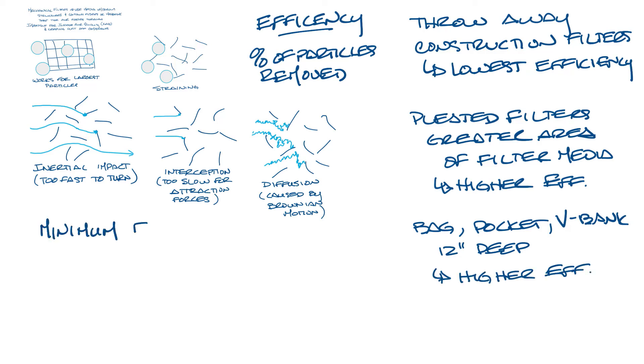You'll see filters rated with a minimum efficiency reporting value or its MERV value. So you'll see MERV 8, MERV 13, and so on to MERV 16. For the filter types we just discussed, the throwaway filters are typically a MERV 5 or lower. Pleated filters are around MERV 6 through 11. And the V-bank type are usually MERV 11 through 15. I'll do a separate video on MERV and particle size and go into a lot more detail about this later.